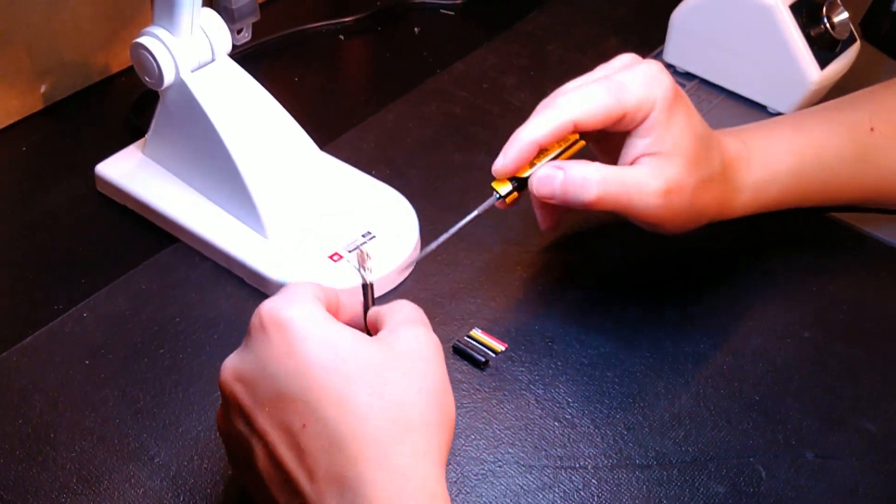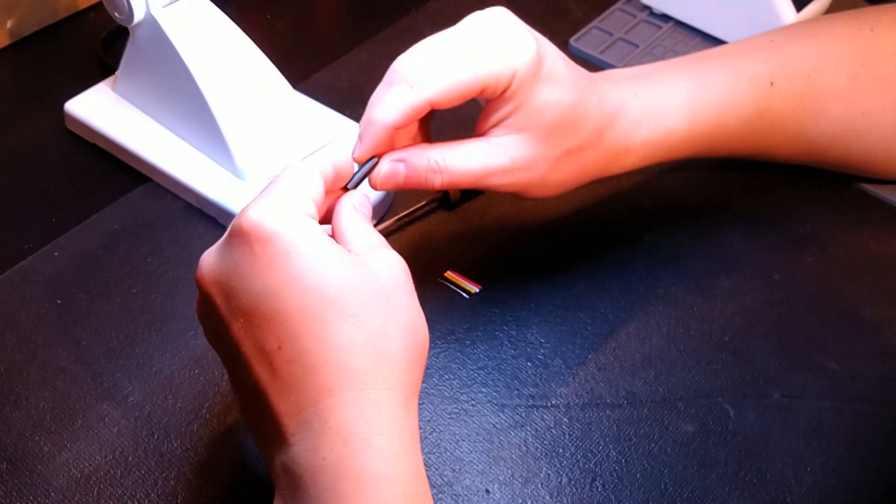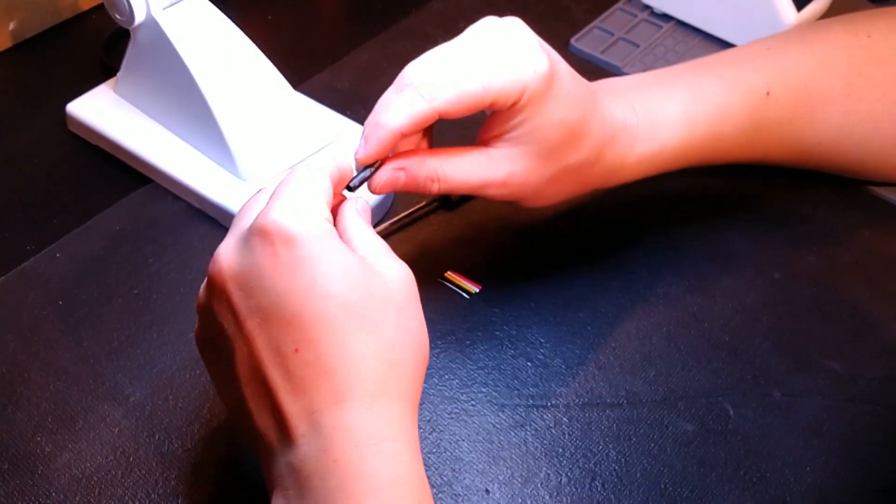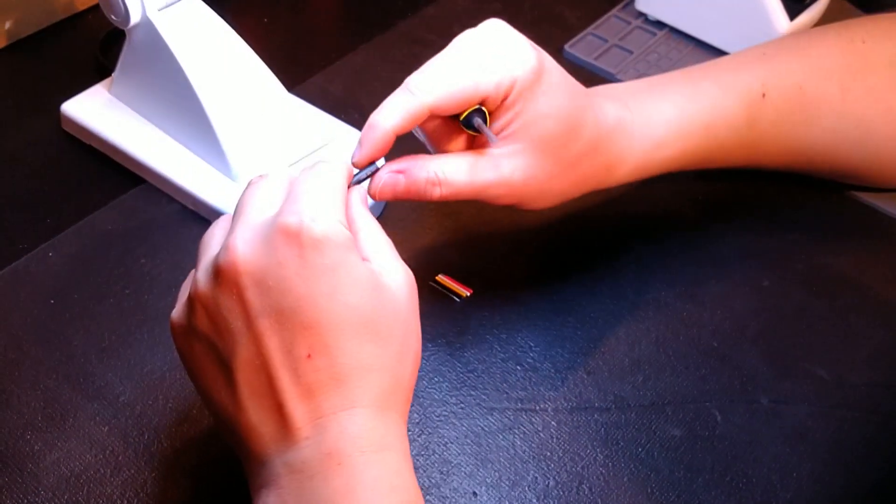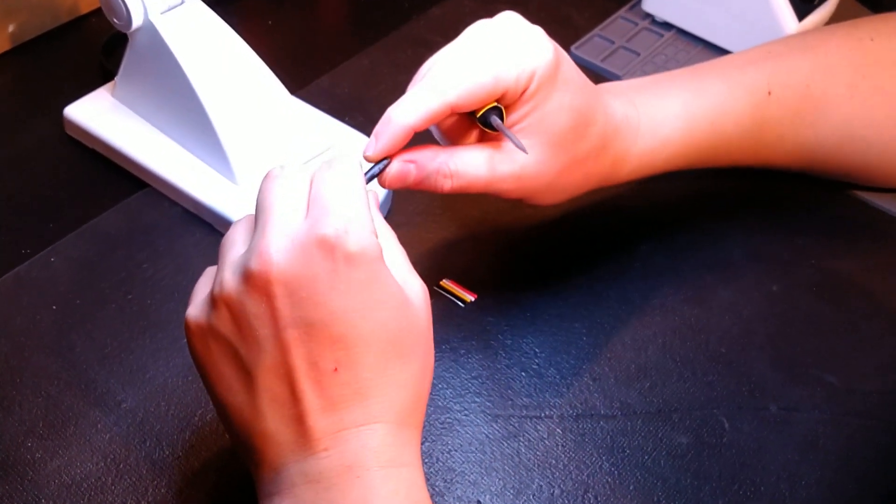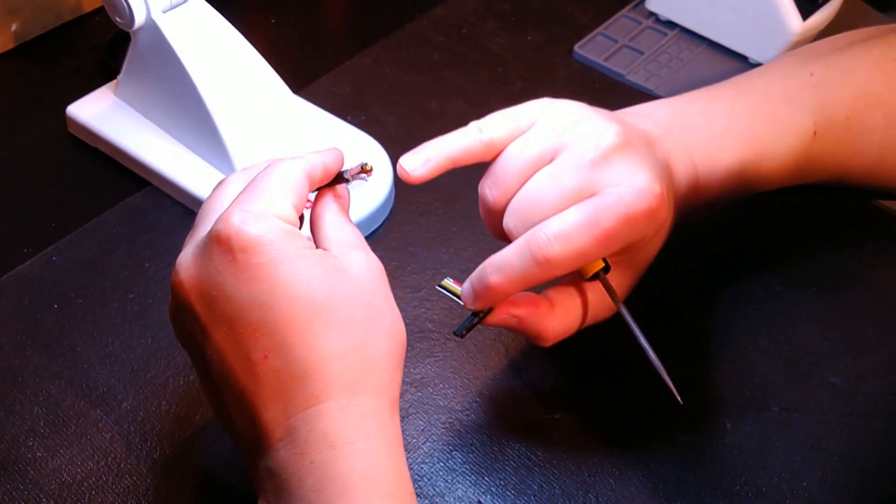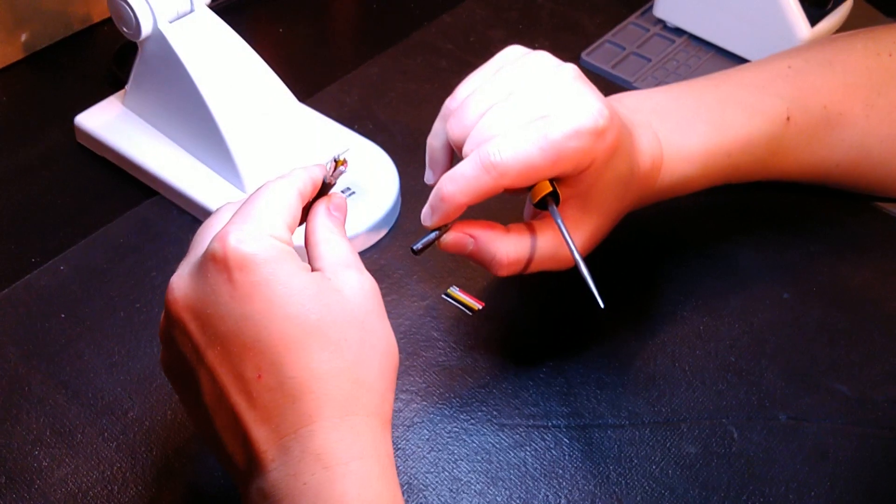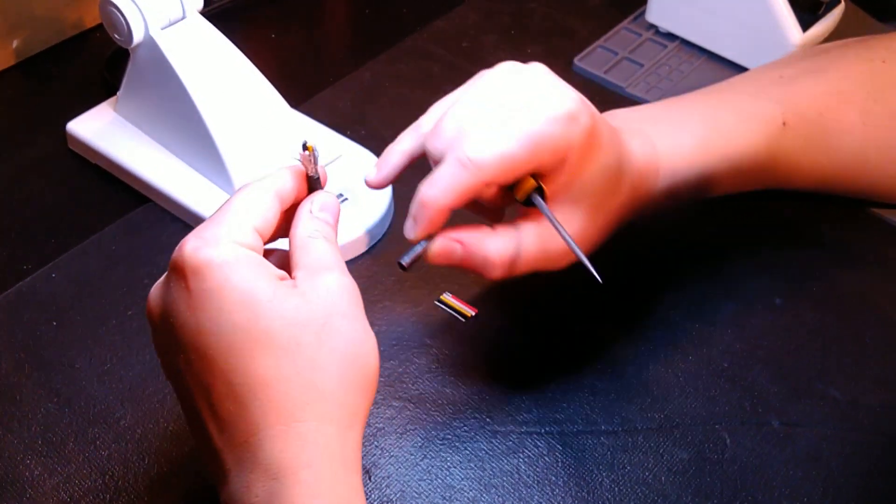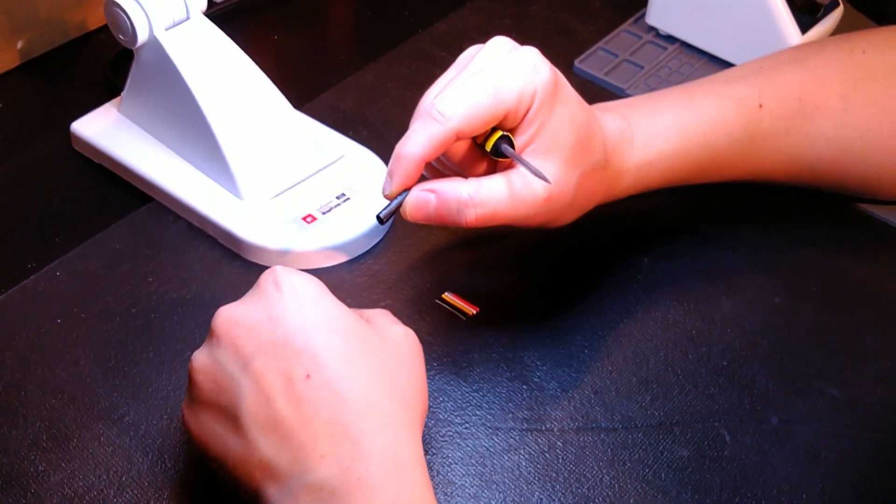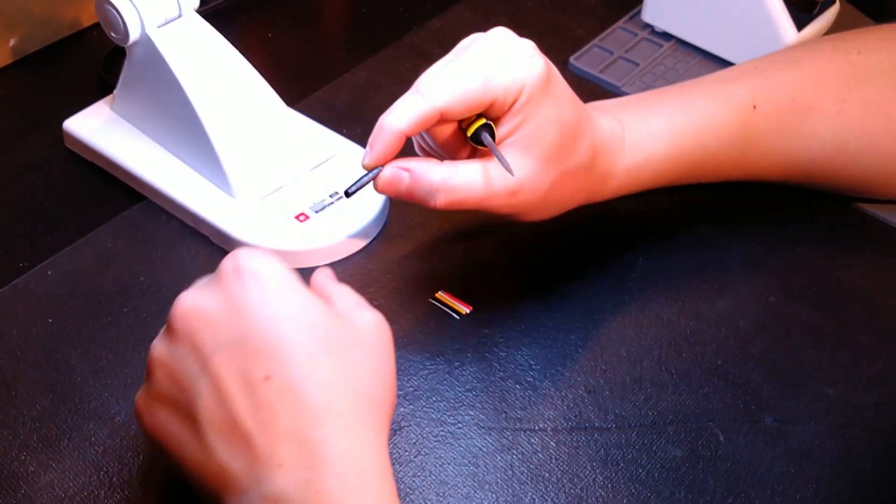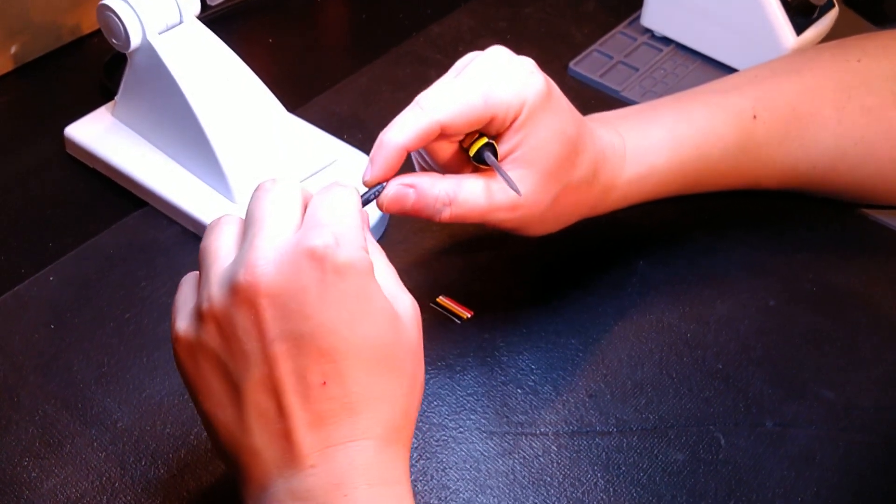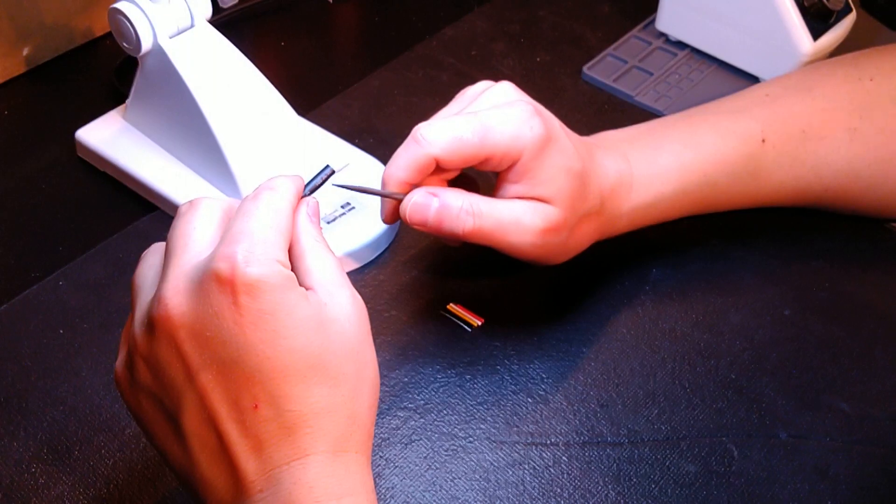Another thing I did—I wanted to add more flexibility to the cable because for motor cable use you want as much flexibility as possible in the cable chain. I reformulated the PVC insulation so we have more flexibility, and I was able to remove the twine inside the cables so that your flexibility was there but we reduced the friction. Overall cable quality is excellent; we just wanted to make sure the flexibility could be even greater while still retaining the same principles and specs.